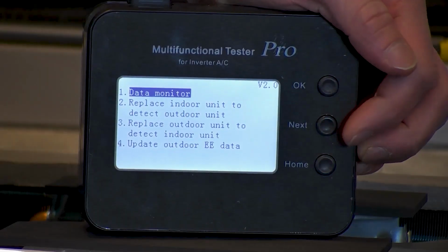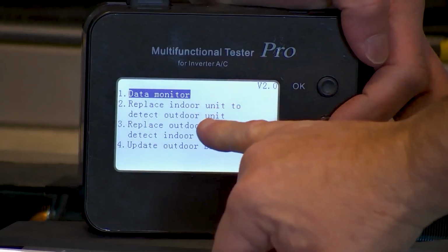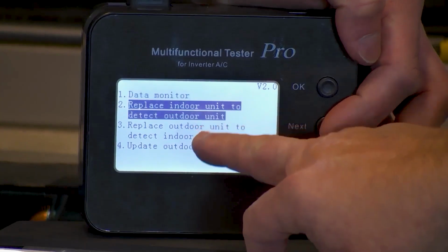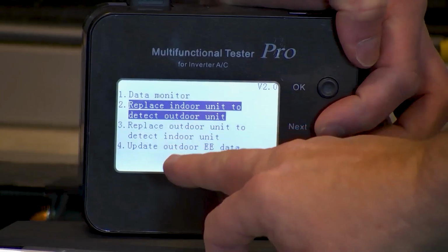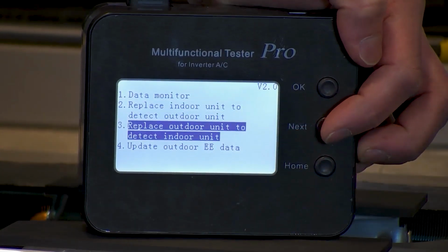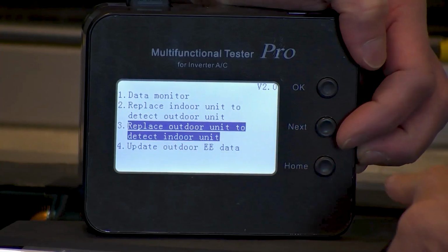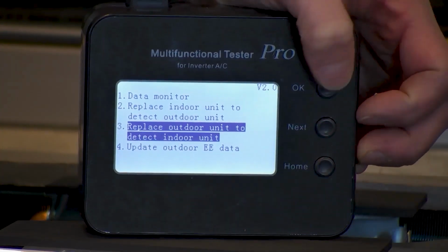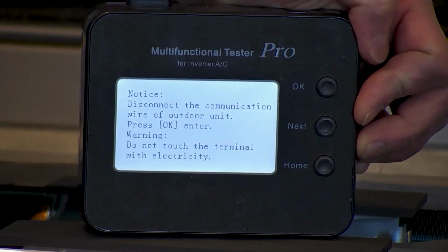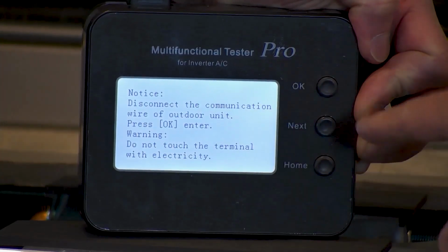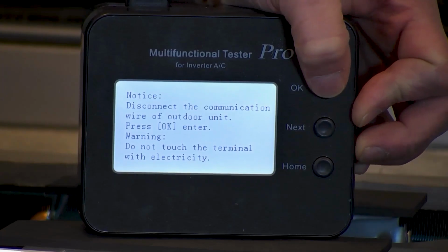Okay, so the first is data monitoring. The second was replacing the indoor. We're going to go to the third one, which is replace outdoor unit to detect the indoor unit. We're there, so hit OK. And then it tells you what to do as far as wiring and stuff. Hit OK again.